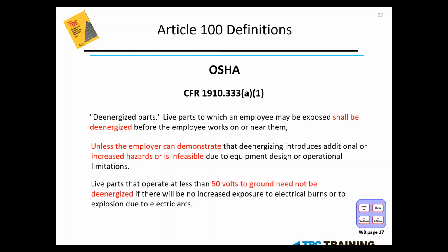The third instance, live parts that operate at less than 50 volts to ground need not be de-energized. So the 3 in sum are 0 to 50 volts, while troubleshooting, also known as infeasibility, and number 3, where it could create a larger hazard to shut it down, such as life support systems, certain types of alarms, releasing toxic gases, chemicals, liquids, and so on. So these would be the 3 instances that the employer would identify as being necessary to work energized.